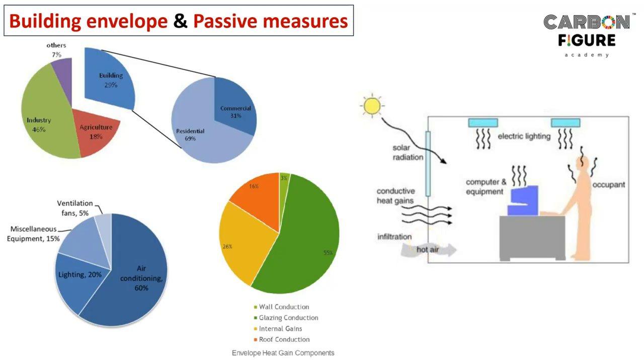If it is completely concrete, then no infiltration is possible. But if you have a steel-based, curtain-based, or wooden-based envelope, there is a little possibility of hot air infiltration. Apart from that, conduction-based ingress would be the major dominant entry.